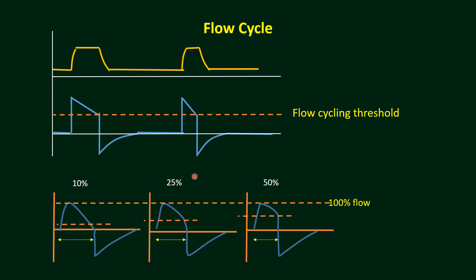And the same thing happened in 50%. Here 50% of the flow is achieved and inspiration ended. So here 10%, 25% and 50%. When flow cycle is 50%, inspiratory time becomes much shorter, inspiration ended early, and when it is 25%, inspiratory time is a little longer, and when 10% flow cycle is given, inspiratory time is much larger. So you can adjust inspiratory time in pressure support ventilation this way. You cannot set inspiratory time directly. So this is flow cycle.